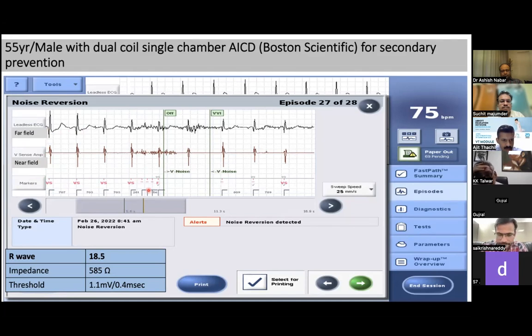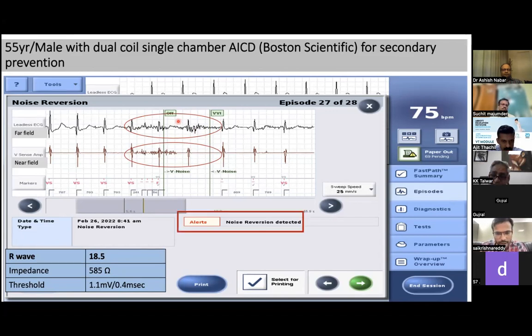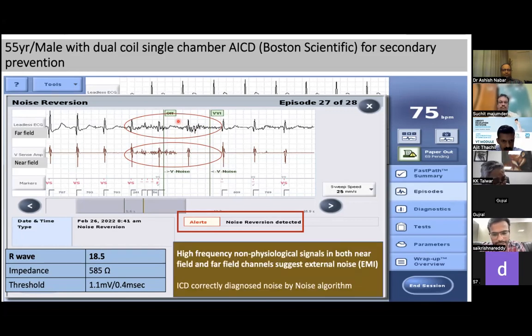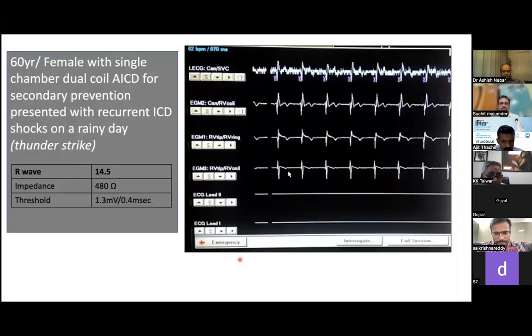Now if you see, we have very high frequency, almost non-physiological, instantaneous signals, and then bizarre signals, which are intermittently seen in both far field as well as near field. For the device, if such non-physiological, bizarre, intermittent signals are seen in both far field and near field, it is labeled as noise, which is appropriately detected by the device as noise by the noise reversion algorithm. So this is appropriate function by the device. Any high frequency non-physiological signals seen in both near field and far field are labeled as noise by the device, which is correctly done here.